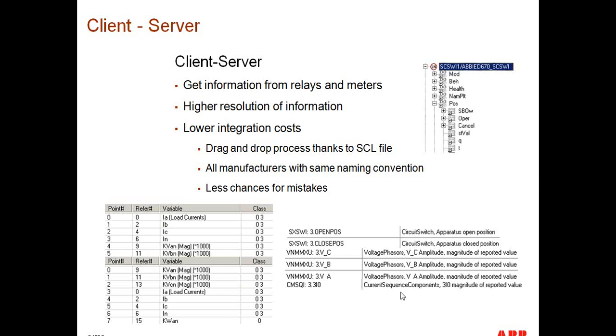The reason for this is that every IEC 61850 enabled device is going to have its data model. Since it's standard and there's a language to document this information called SCL, or Substation Configuration Language, every device from every manufacturer is going to have this mapping available in the form of either a CID or an ICD file. The idea is that you can grab that file, and then you will know what functions are available inside that particular device.